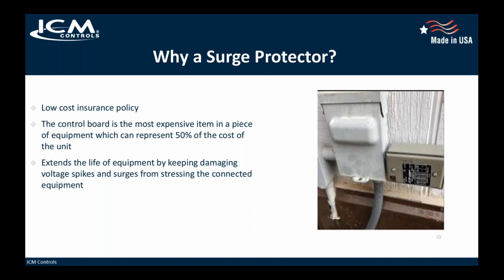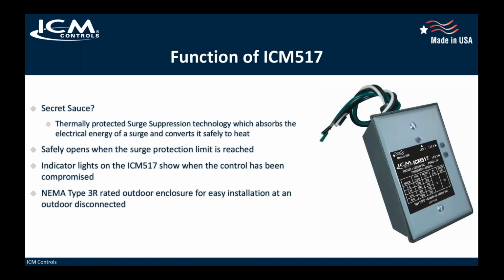So the question on this slide is, why do you need a surge protector? This picture shows one of our surge monitors installed on an outdoor disconnect. Why do you need it? Well, you want to protect your equipment, obviously. The control board in a unit can sometimes represent almost half the cost of the actual product itself. Furnace boards are getting very expensive in some cases. Some Carrier furnace boards are $400 or $500, and they can be extremely expensive. So having something like this on your residential equipment is pretty handy. It extends the life of the equipment and keeps damaging spikes from stressing the components in the equipment, and especially the circuit board itself.